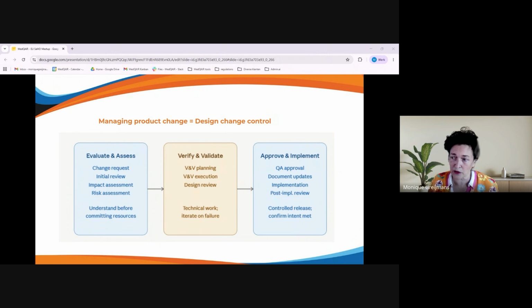Part of development is updating your requirements if needed, and updating verification and validation. So that's a planning activity too for your design and development, and then your execution. Validation: you also need to check if the change has impact on your validation evidence, but that depends of course on the type of change you're trying to bring in. Design review is always part of this cycle, to conclude that you have done and touched everything that is needed for the change to be implemented. And do it iteratively. If you are making changes and there is a failure, then go again. That's normal software development practice, so I would not expect that to be a surprise to anyone.